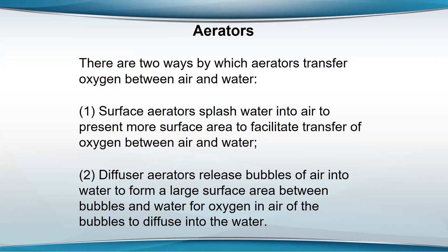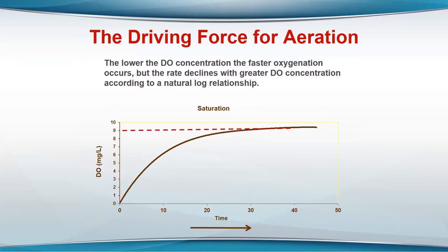The driving force of aeration is the difference in the oxygen concentration of saturation and the oxygen concentration of the water. Aeration is much more efficient at zero oxygen, but of course all your fish would need oxygen before that. You're going to have to operate somewhere around three parts per million, and the aeration is only going to be operating at maybe 50 to 60% of its efficiency compared to what's calculated in standard tests at zero dissolved oxygen.